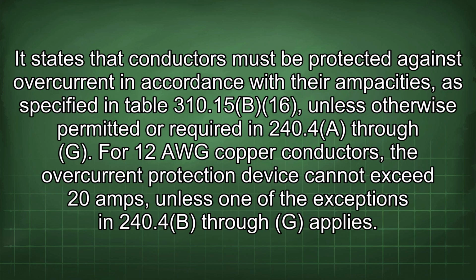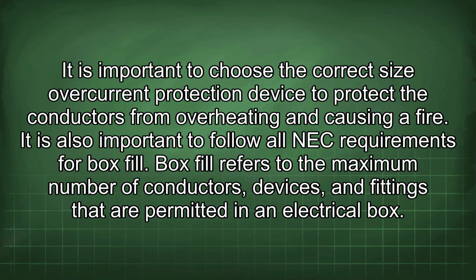It states that conductors must be protected against overcurrent in accordance with their ampacities, as specified in Table 310.15(B)(16), unless otherwise permitted or required in 240.4(A) through (G). For 12 AWG copper conductors, the overcurrent protection device cannot exceed 20 amps unless one of the exceptions in 240.4(B) through (G) applies. It is important to choose the correct size overcurrent protection device to protect the conductors from overheating and causing a fire. It is also important to follow all NEC requirements for box fill.